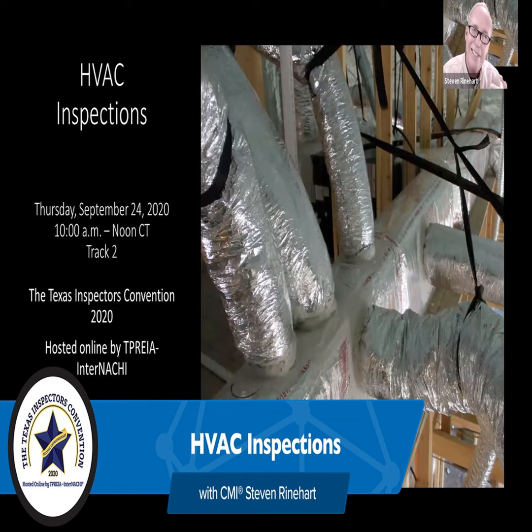I've seen ducts sweat enough in an attic to drip. So that could be an issue. I haven't ever written it up as a defect. When I see a big ball of ducts, I'm usually feeling around them because I turn the unit on one way or the other. So when I'm in the attic doing the inspection, the blower air handler is running, and I'm feeling for air leaks.